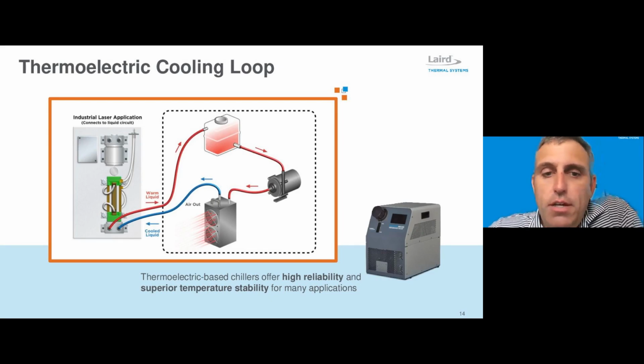If we take a quick look at the insides of one of these thermoelectric chillers, within the dotted line here, similar to the refrigeration systems and any of the liquid cooling systems that we supply, they have a tank and a pump that's used to circulate the fluid. But the cooling is actually taking place within a thermoelectric or a Peltier device. So what we have here is a liquid cooled block that's mounted to the cold side of the thermoelectric, and the thermoelectric acts as a heat pump to pump the energy out of the liquid block through the Peltier and then into a finned heatsink on an air side of the Peltier. And so this is the general concept under which they work. These systems also, because they have lower cooling capacities, tend to have lower flow rates, and so this is really conducive to mag drive pumps. Magnetically coupled pump motors are even more reliable since there's no mechanical seal that can potentially leak over time.